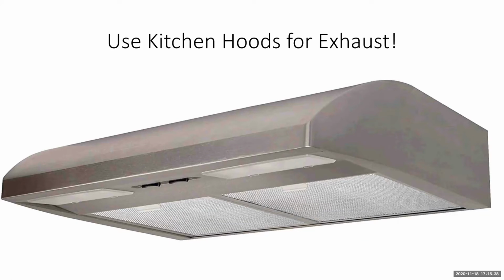But if you have an electric range, which I assume you're all using, you still have a fair amount of combustion of oils and humidity. ERVs and HRVs have relatively low exhaust rates. They might be 20, 40, or 80 CFM, but what you actually need is about 250 CFM to get about 80% capture of combustion fumes.